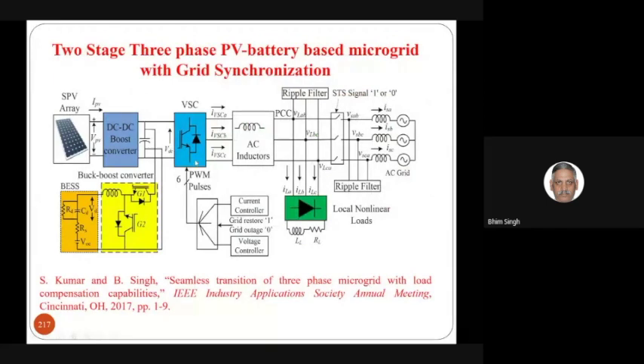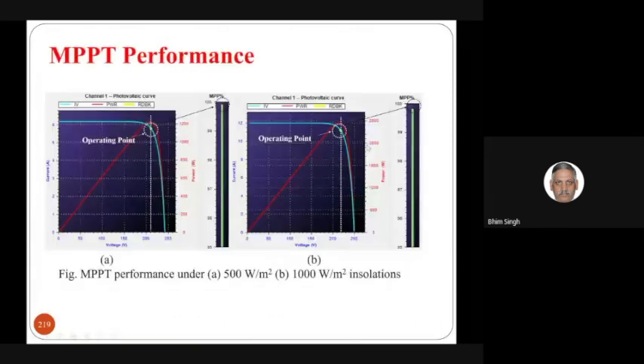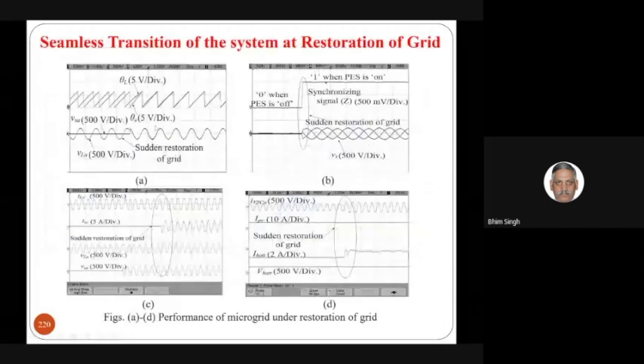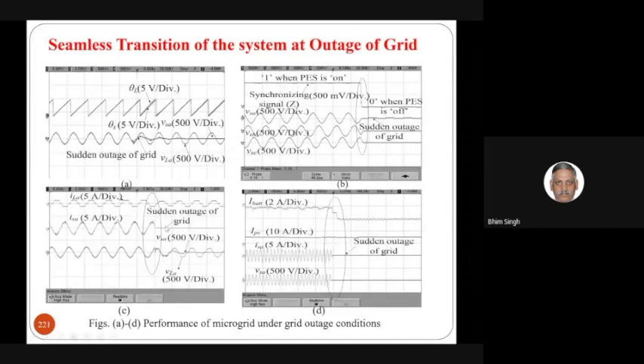And this is the same thing extended for 3-phase, with the battery and the buck boost converter, and we have a 2-stage system for islanding mode as well as synchronization mode. And this is the control of that, and you are able to see that when the grid appears and you start synchronizing, then we close the switch to the grid after 3 cycles. So the grid appears here, and after 3 cycles it closes the switch to the grid. It is a seamless transition that takes place here.